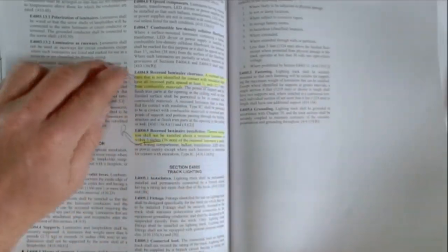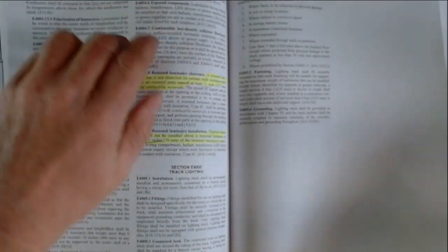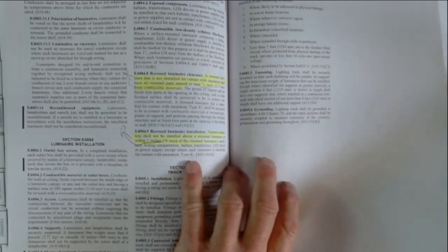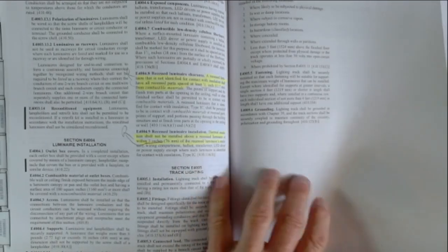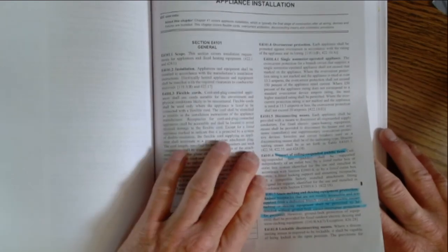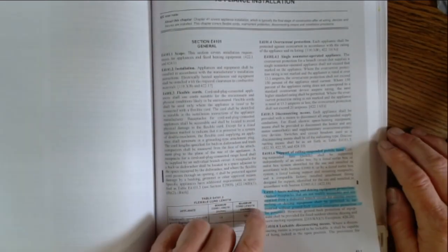I just know this about offsets from recessed lights. No, this is important: half an inch from recessed light to combustible construction, or 3 inches to insulation, unless it's specifically designated otherwise, which the new ones, the LEDs, usually are. You don't need to do that anymore. Snow melting does not need to be ground fault protected. Keep that in mind.